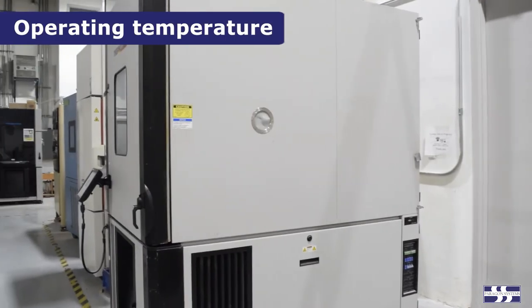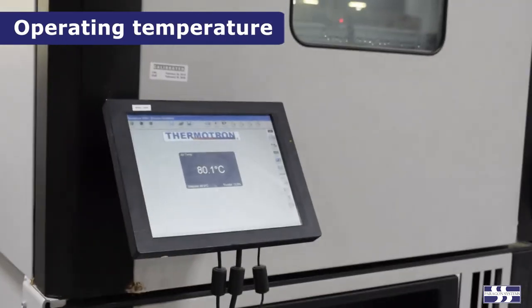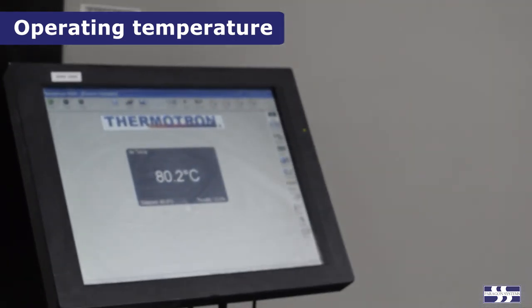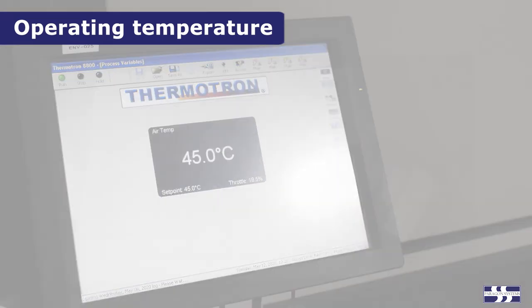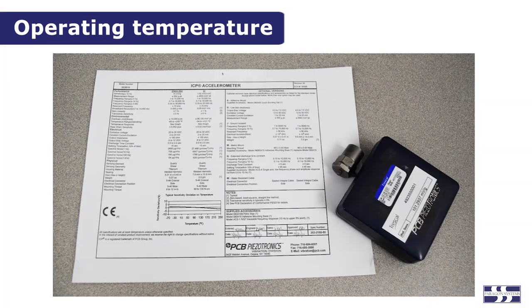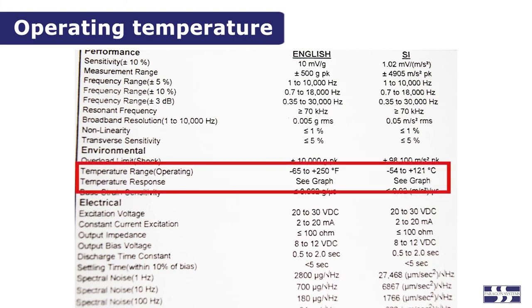The temperature which an accelerometer is exposed to will affect its sensitivity, and can significantly change the acceleration values that you are measuring. Again, the manufacturer's specification for the accelerometer should be consulted to ensure that the accelerometer will measure accurately at the temperature under which you are testing.